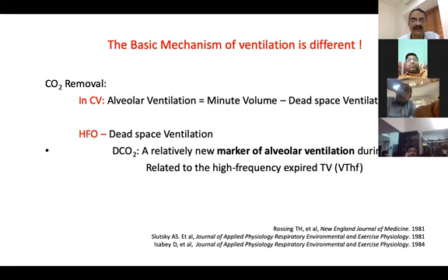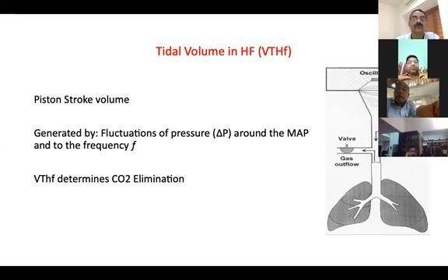Tidal volume, or in high frequency, the VTHF, is actually the volume that is generated when the piston moves in and out. So this is never more than the dead space ventilation. And it's actually generated, all of us know, by the variations of pressure, the delta P around the mean alveolar pressure. But this has a phenomenal effect in eliminating CO2. So this is a VTHF. Now, we also know the basic principle, which I am just repeating to emphasize my concept, that tidal volume is actually determining your CO2 elimination, the stroke volume, or DCO2, whatever I was mentioning previously.